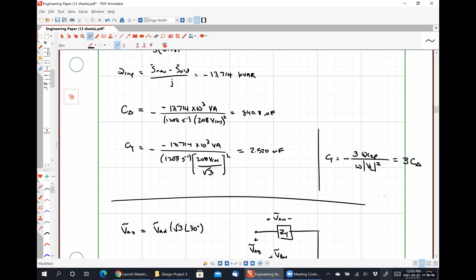But that is the biggest thing if you're doing power factor correction to watch out for: that voltage drop over the capacitor, because what number you use depends on A, what you were given, and B, whether you want a line-to-line voltage if your capacitor bank is in a delta configuration, or a line-to-neutral voltage if your capacitor bank is in a Y configuration.